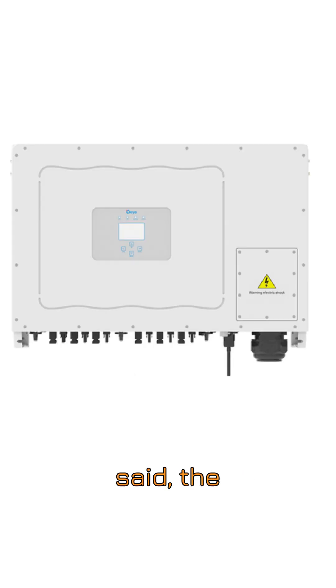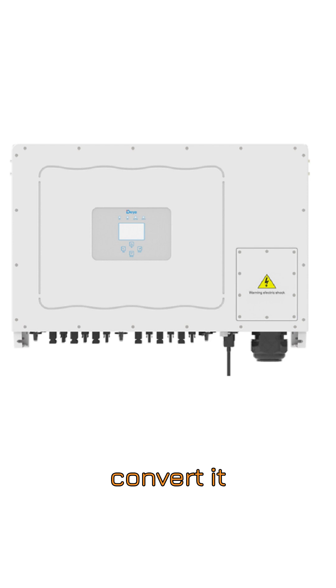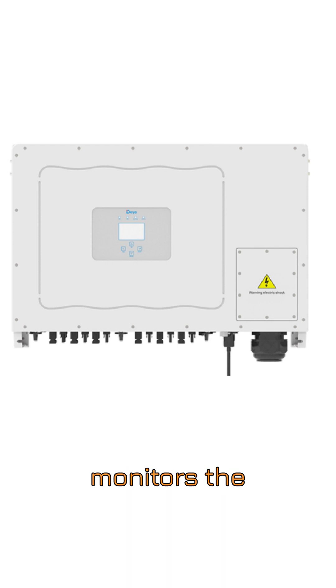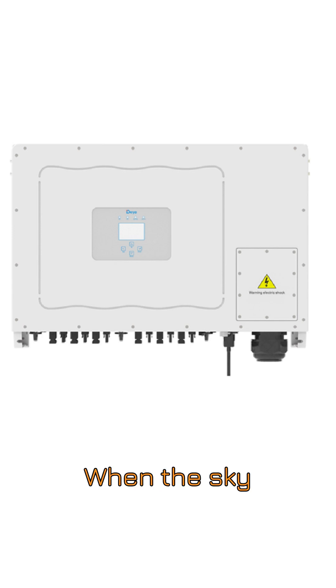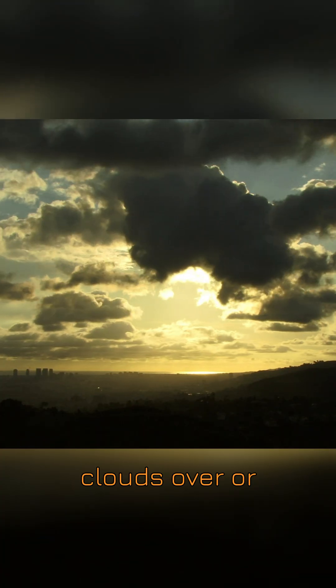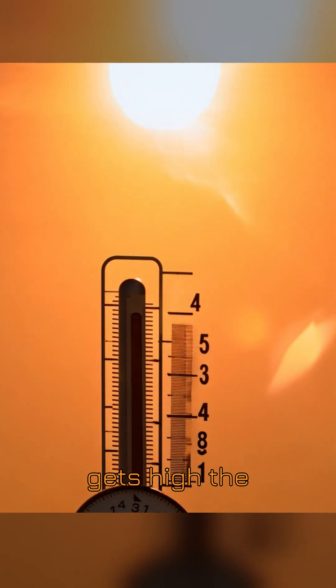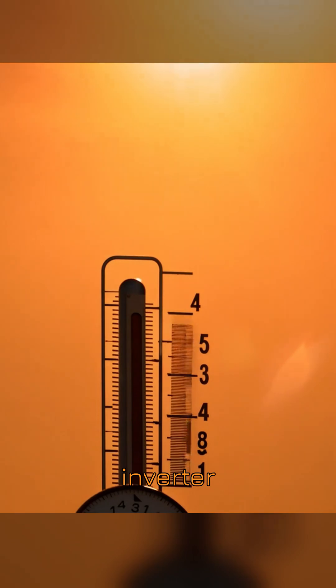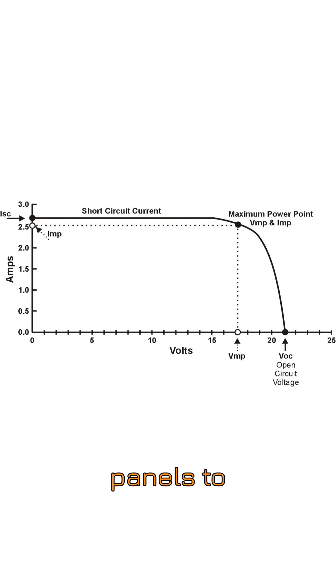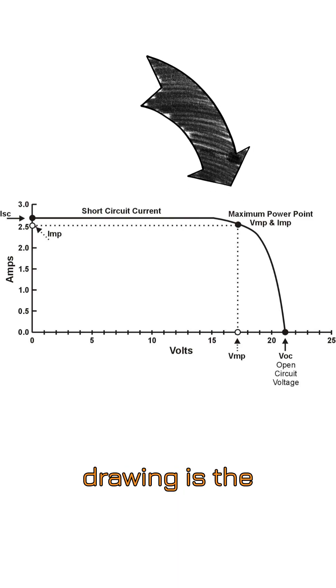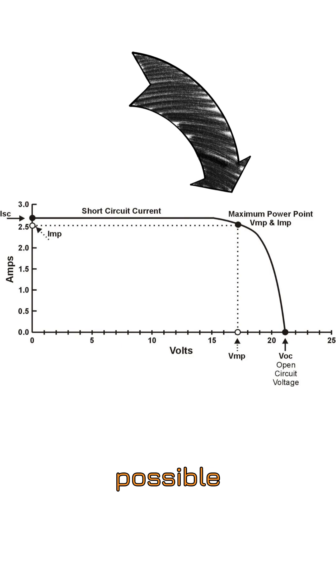As we said, the inverter doesn't just convert. It plays the role of a smart regulator. The inverter constantly monitors the current's voltage and amount. When the sky clouds over or the panel temperature gets high, the inverter automatically adjusts the load on the panels to ensure the power it's drawing is the maximum possible power.